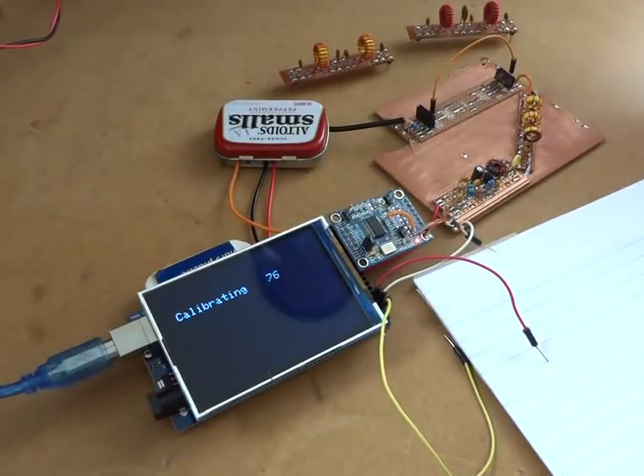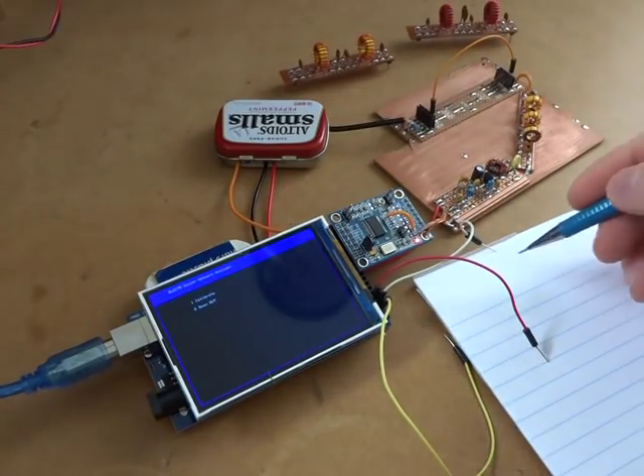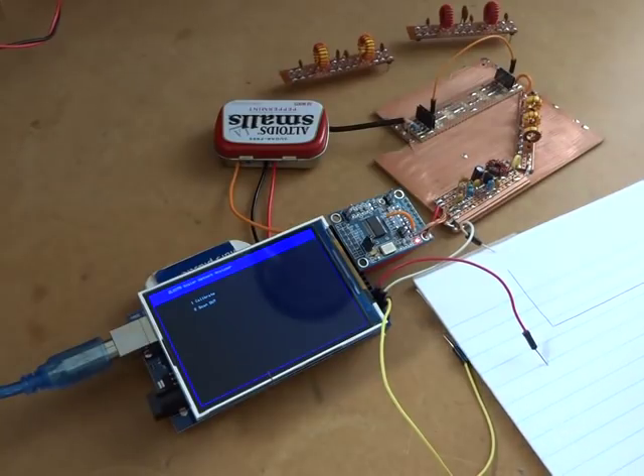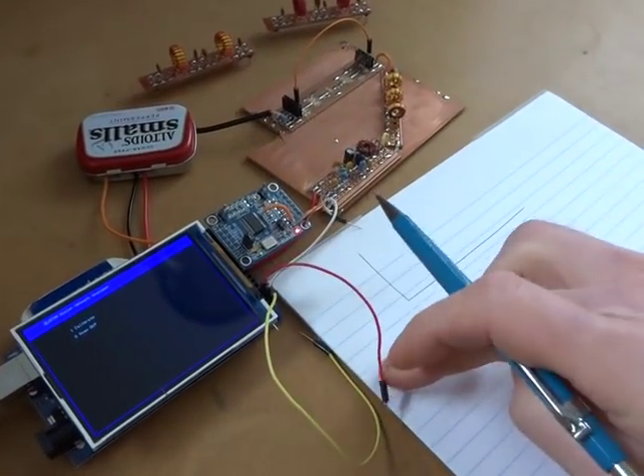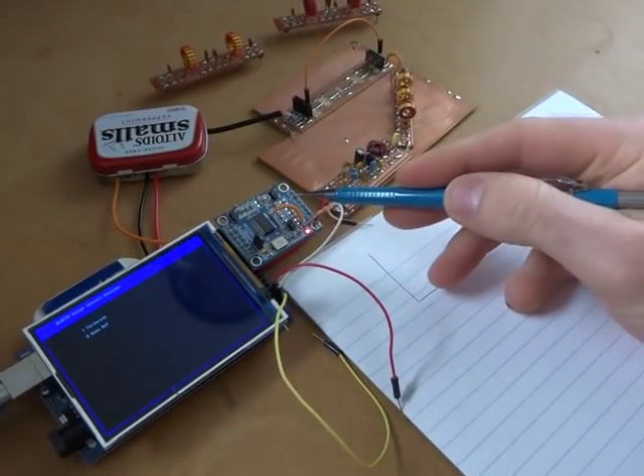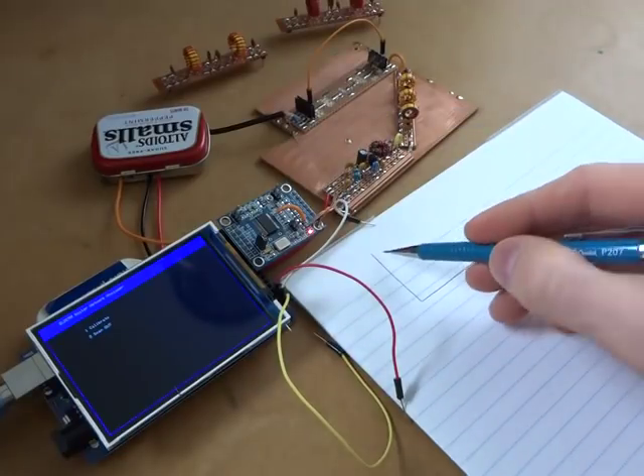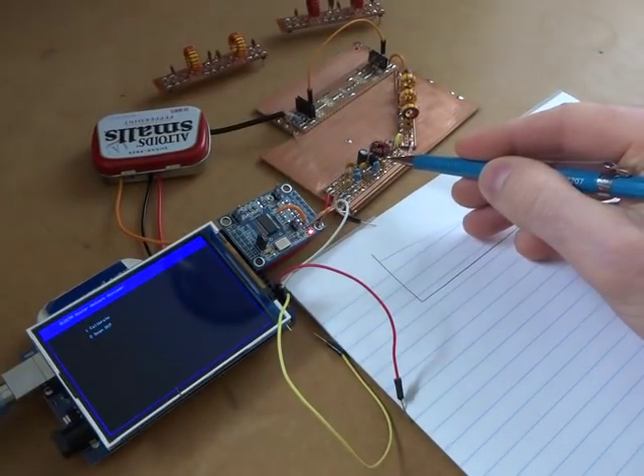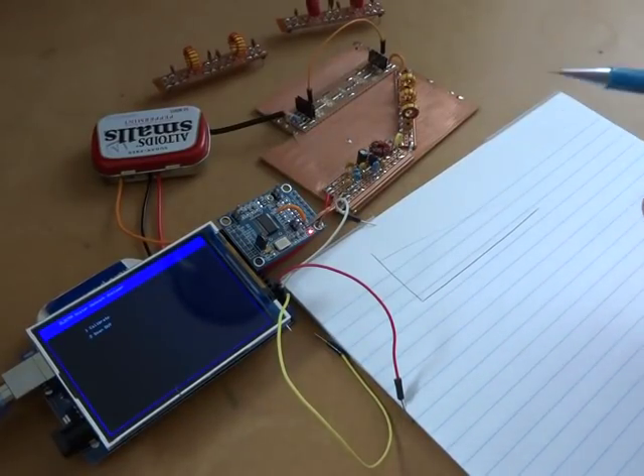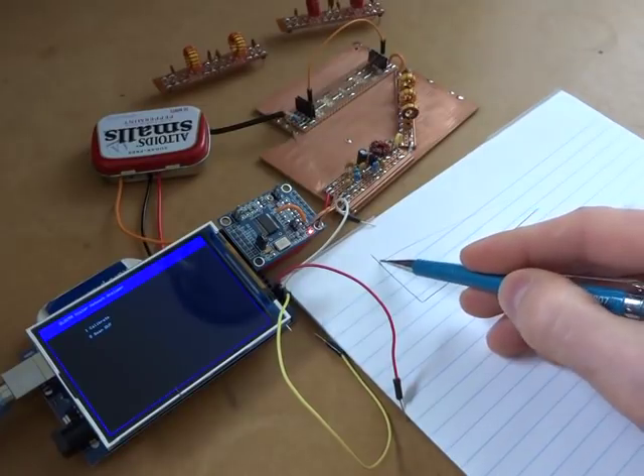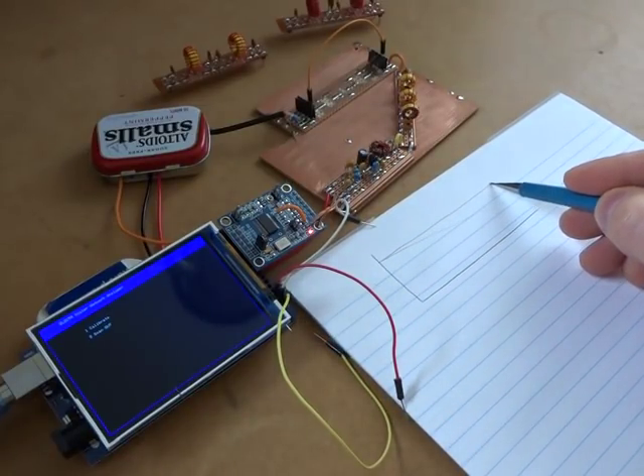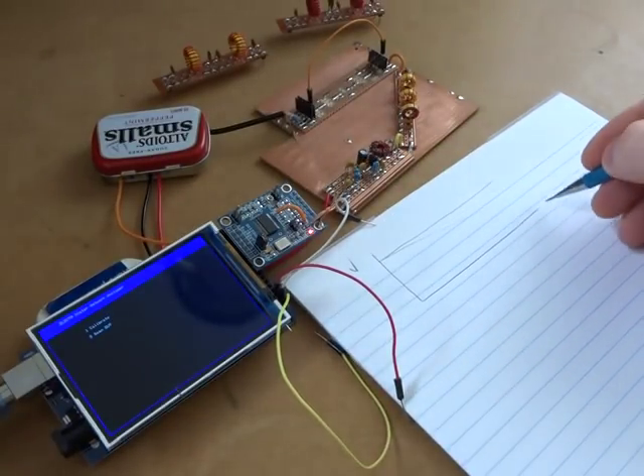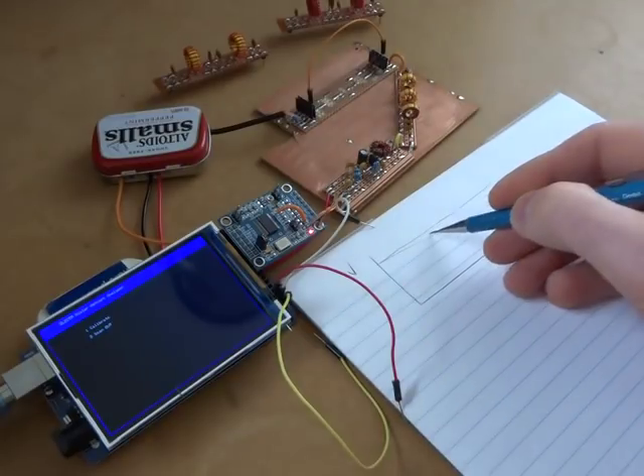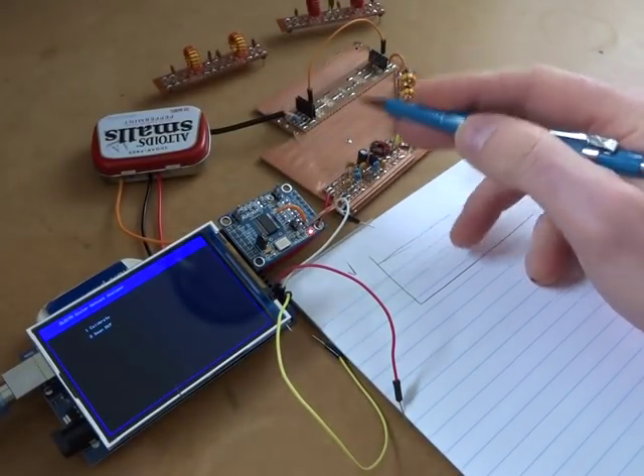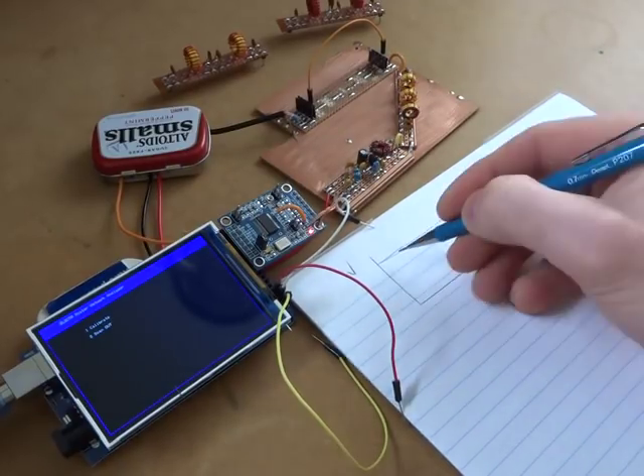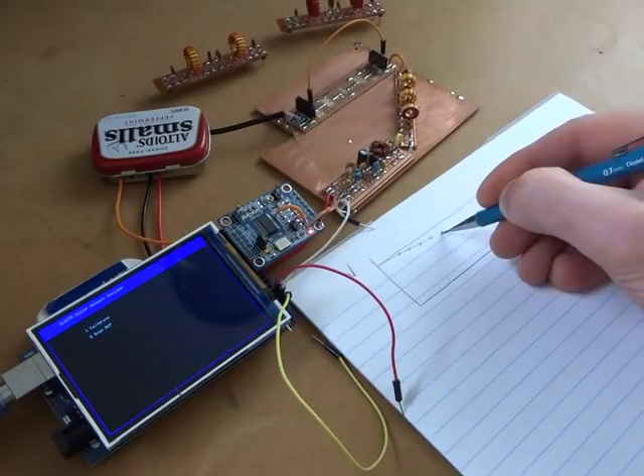That's in percentage. And if I was to draw what's happening, let me zoom up on that. We know that the output of the 9850 will slowly drop off, as well as the amplifier. So in an ideal world, we want to present to the device under test a standard or constant voltage across the frequency range, so F down here. But we know that it's dropping off, so at the moment we've got a calibration array, and we'll look at the software in a sec, and we're just taking a series of readings across that frequency range.